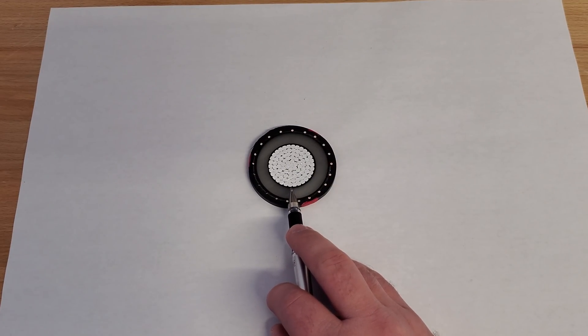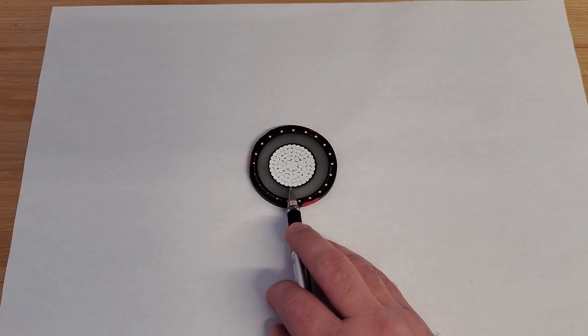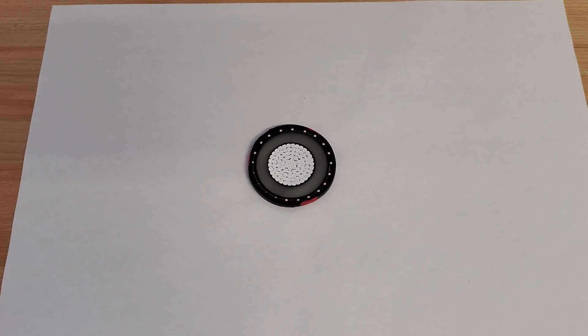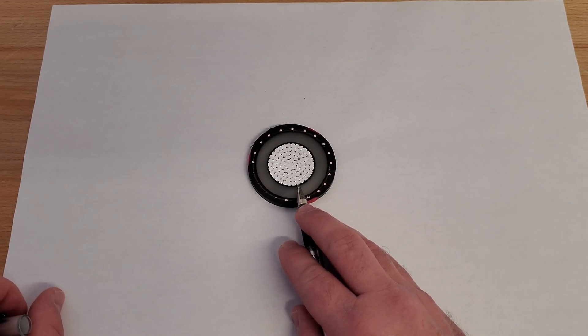The next layer is the conductor shield. And it's actually an XLPE type of polyethylene, but it's mixed with carbon black. I think the technical name for it is acetylene black. And it actually comes from a byproduct of acetylene. So you've probably seen somebody with an acetylene torch when they first light it. You see a lot of that black smoke and black soot. The process of getting this acetylene black is capturing that and refining it. It's extremely conductive. So they mix that acetylene black with the XLPE insulation. And that's why it's black, obviously.